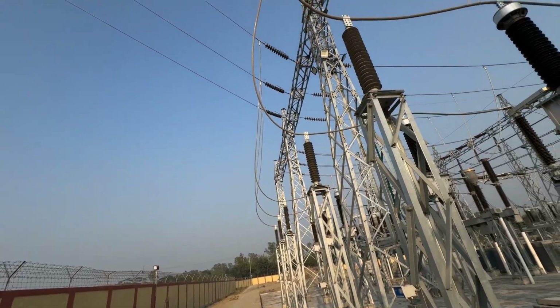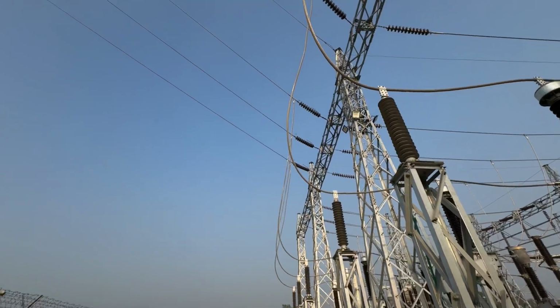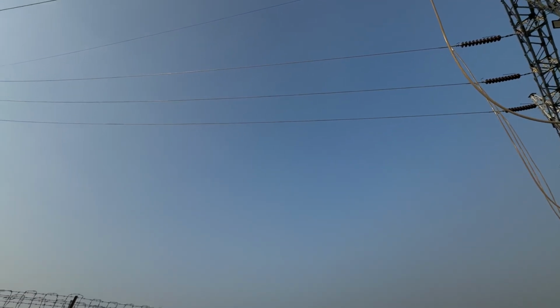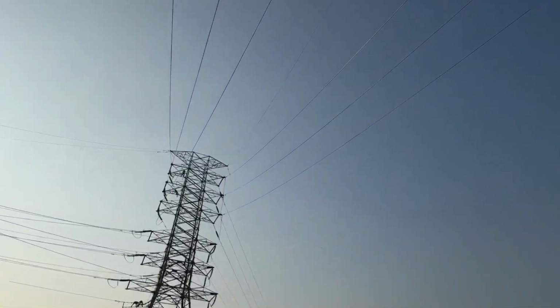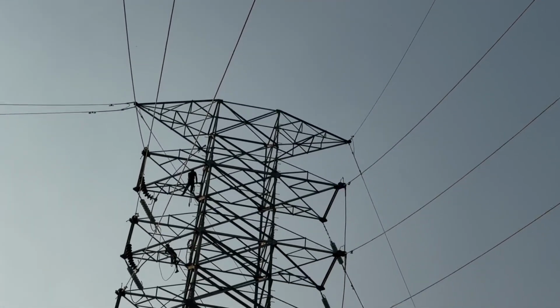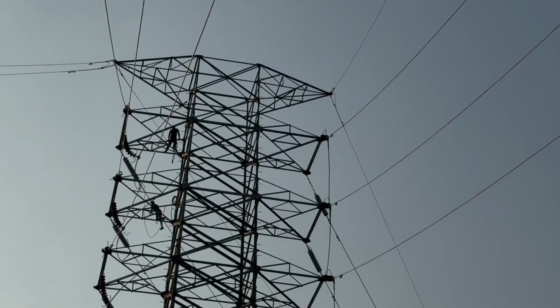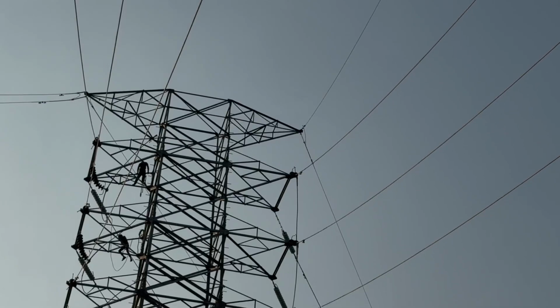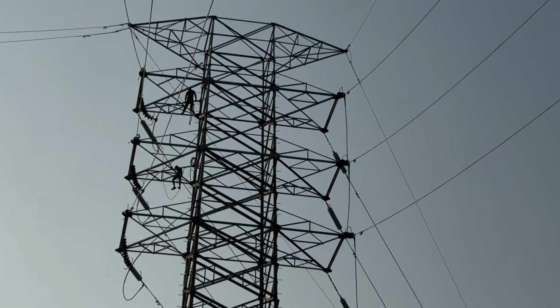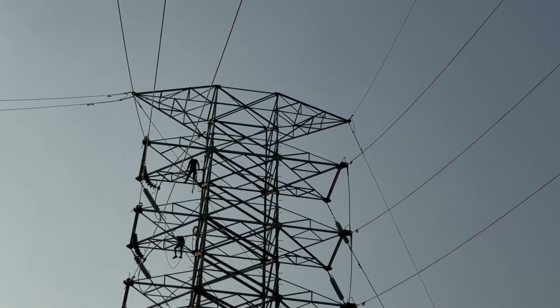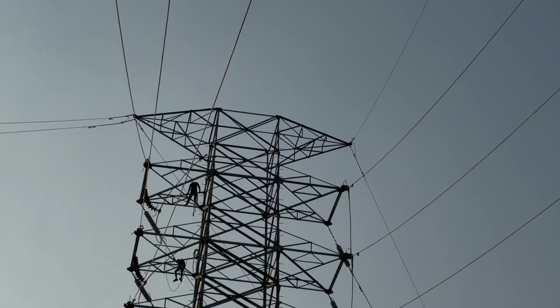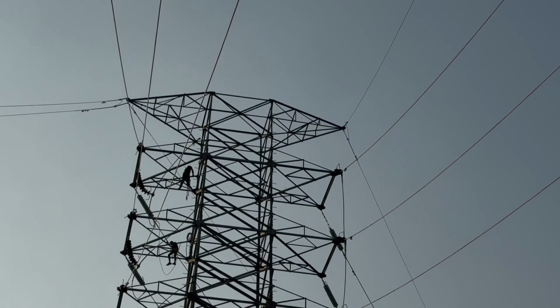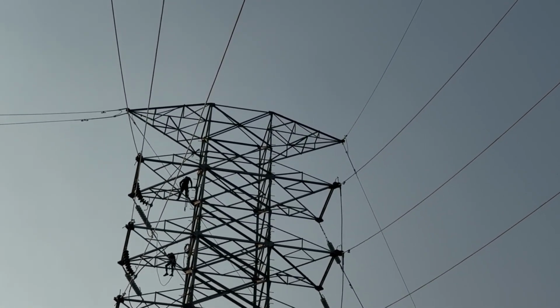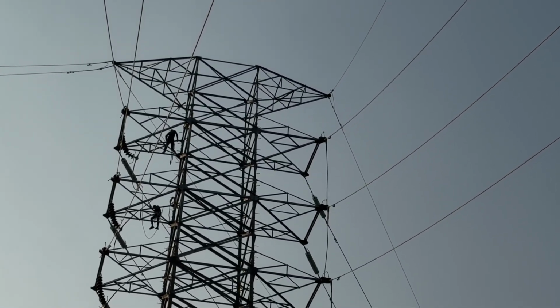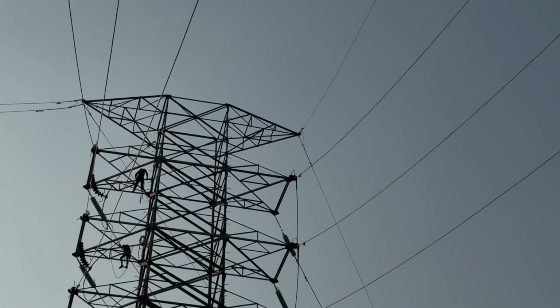be arrested by the conductor also, though there is an earth wire above the conductor through all the line. The upper two connections are earthing wire, the lower three connections are the phase conductors. The upper two wires are earth wires. There are two circuits, so above each circuit there is an earth conductor, so that if any lightning strike comes down from the sky, the earth wire above the phase conductor will arrest this lightning strike and neutralize it by sending it to ground.